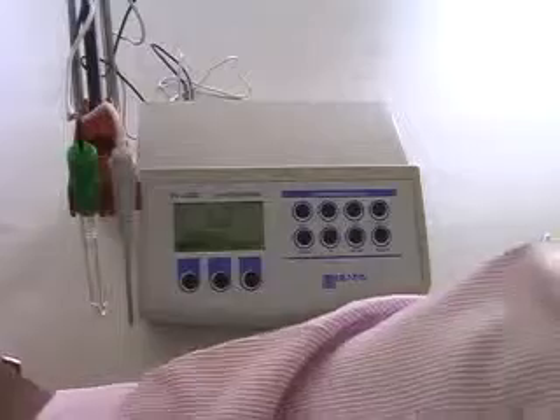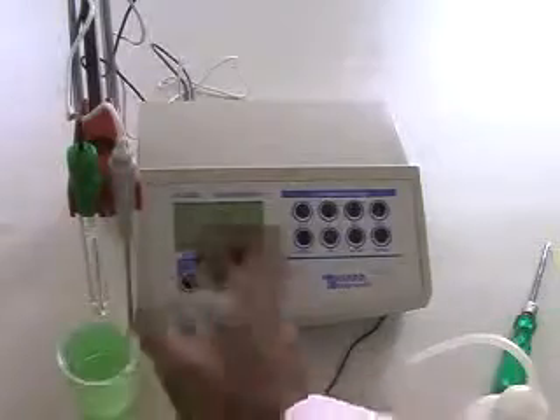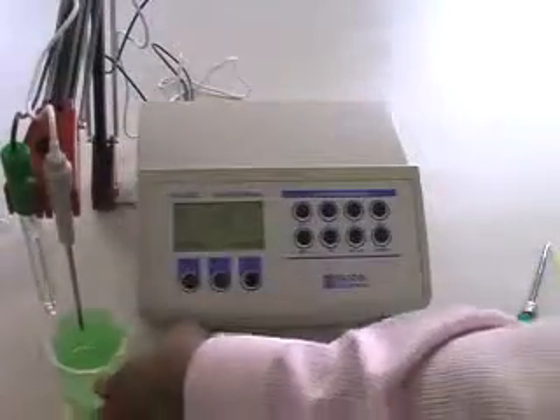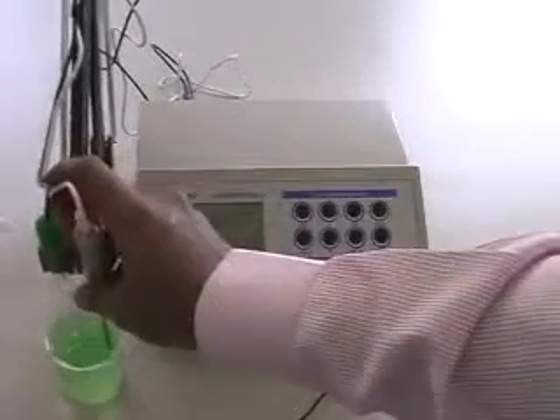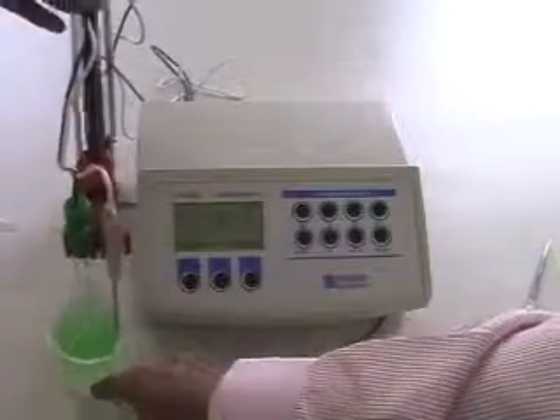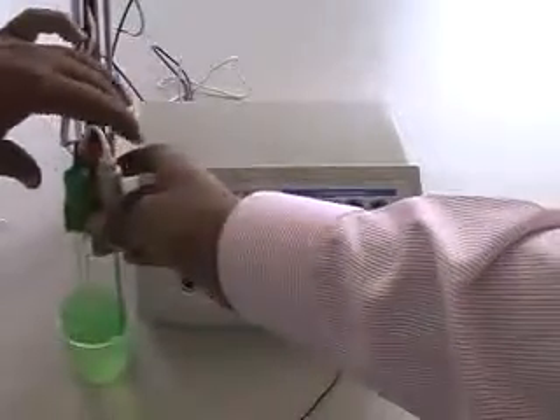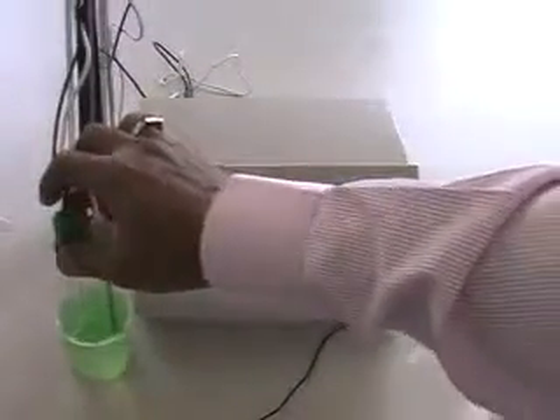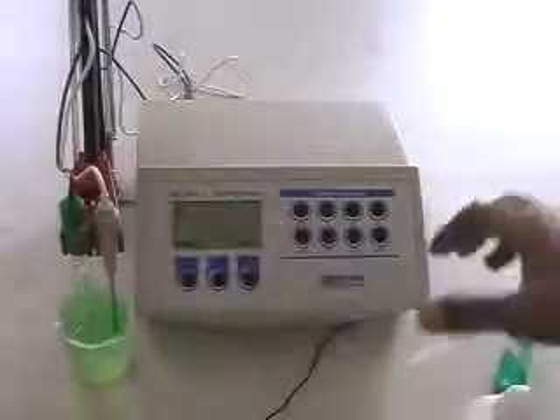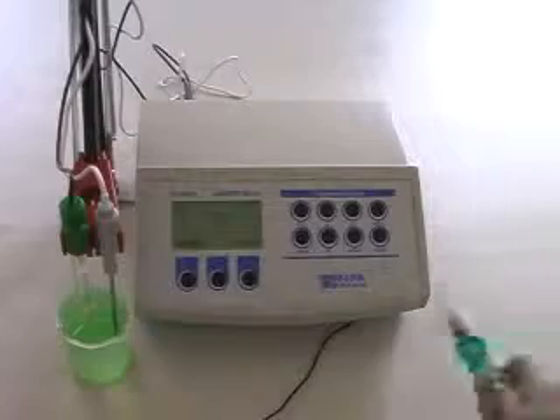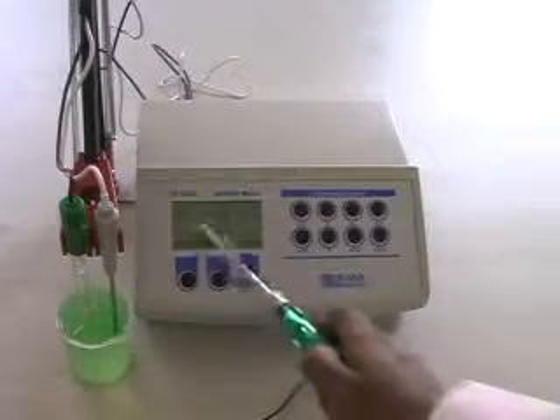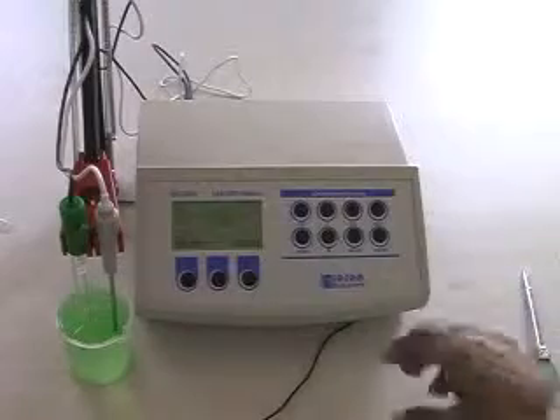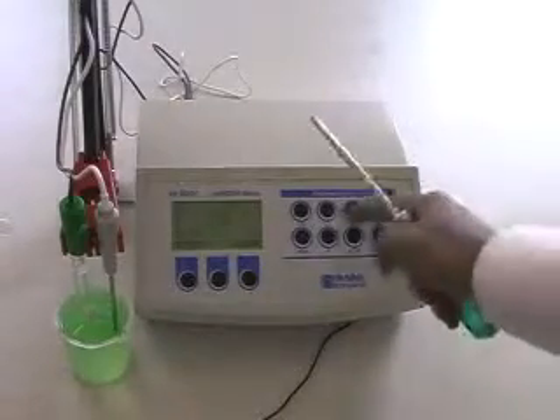Now we are calibrating this instrument for 7 pH and 4 pH. If you have another buffer, you can calibrate with that too. First, this is a 7 pH buffer solution. First, place your electrode and the temperature probe both at one time in the 7 pH buffer solution. So the display is showing the current value 7.01 and the calibration point. To go to the calibration mode, just press this CAL, which means calibration.